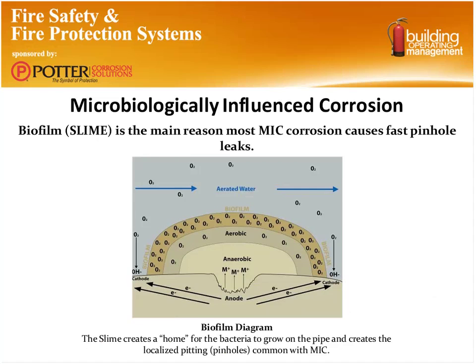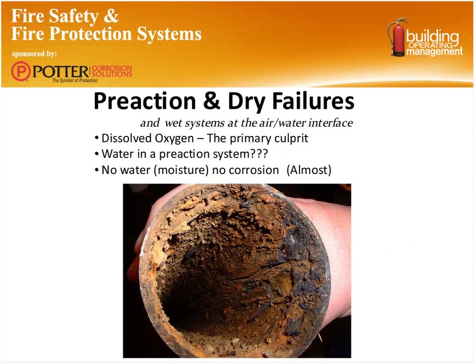If you look at this image here, what you can see is they build their own little safe house, right here. The anaerobic, or non-oxygen requiring, microbes live inside of that shell, and they continue to eat away at the steel within your sprinkler pipes. What that ends up causing are leaks, pinholes, and systems that fail prematurely. We've actually seen these failures in systems in some cases that were 2 to 3 years old.